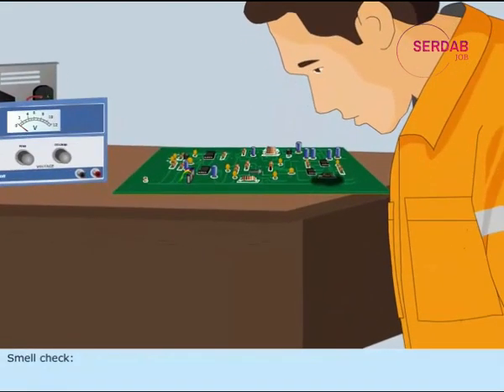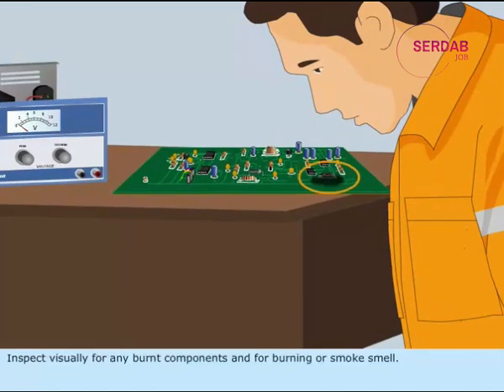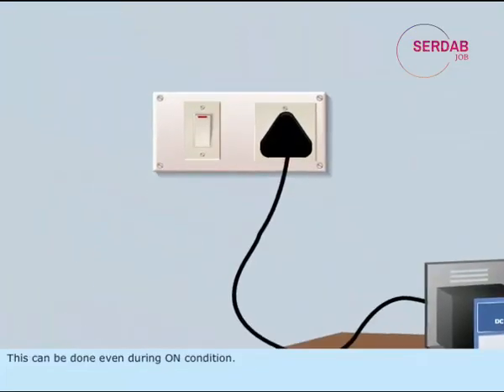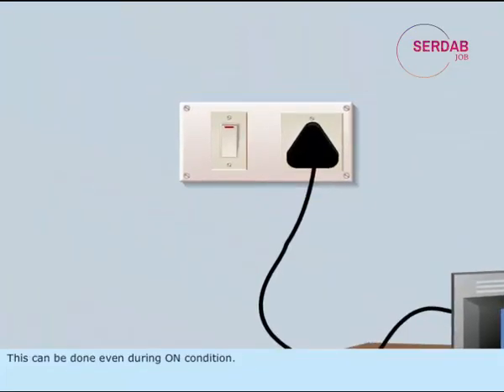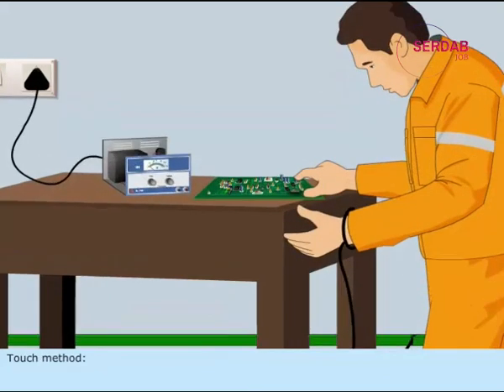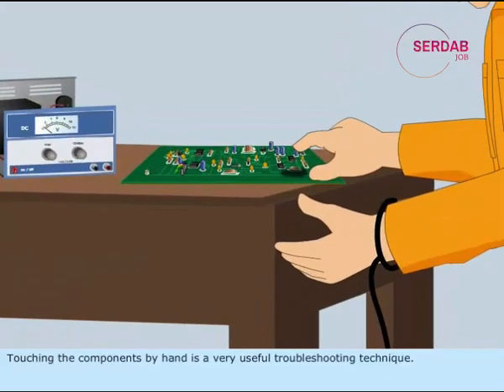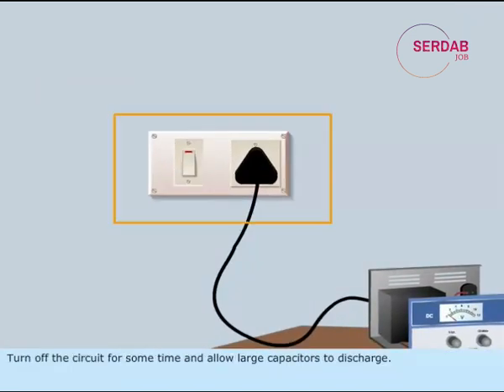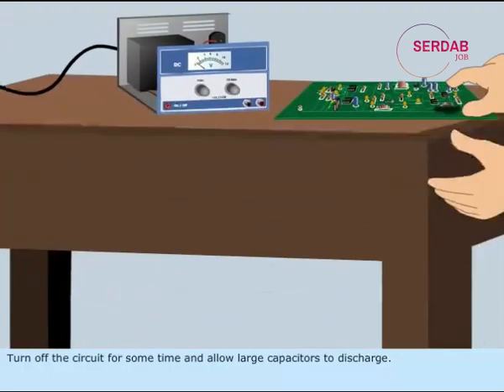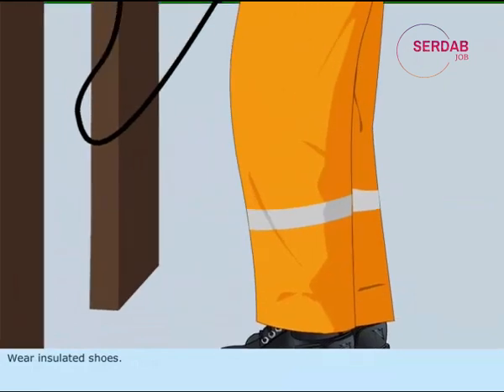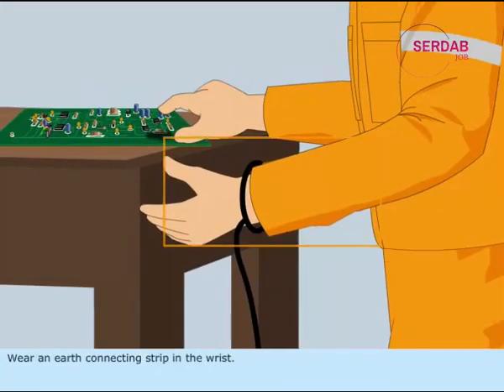Smell check. Inspect visually for any burnt components and for burning or smoke smell. This can be done even during on condition. Touch method. Touching the components by hand is a very useful troubleshooting technique. But take the following precautions before touching the components. Turn off the circuit for some time and allow large capacitors to discharge. Wear insulated shoes. Wear an earth connecting strip in the wrist.